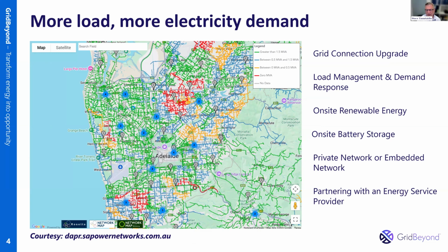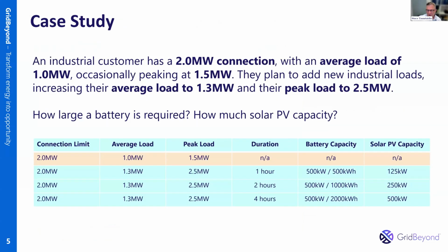So let's look at onsite battery storage. You've made the decision to install a battery after you've done the PQ measurements, you've done your energy efficiency, you've fixed up all your air, etc., etc. So how big is the battery? What sort of battery do you need? And I think James touched on it with his Lamborghini Camry analogy. There's two parameters you look at: the megawatts or kilowatts, or the megawatt hours or the kilowatt hours.